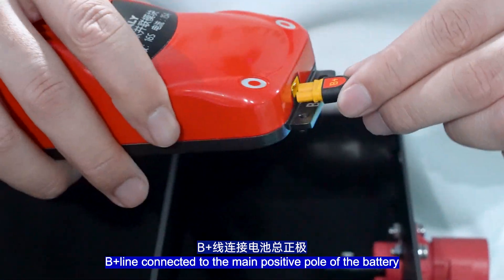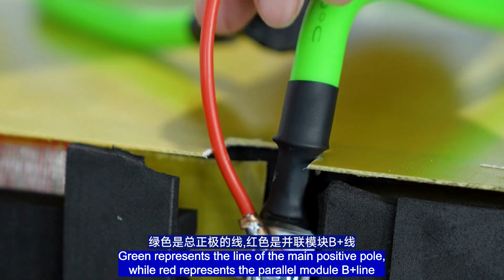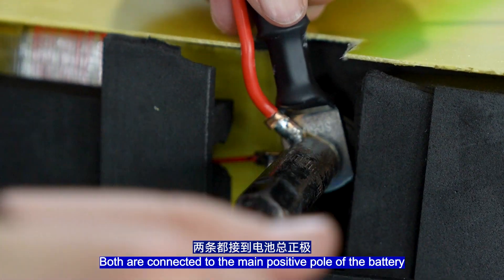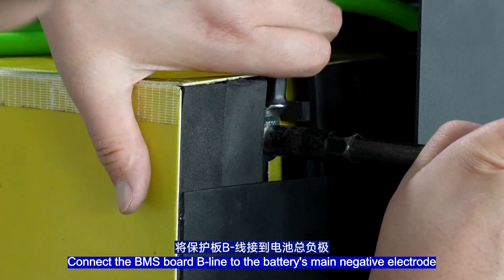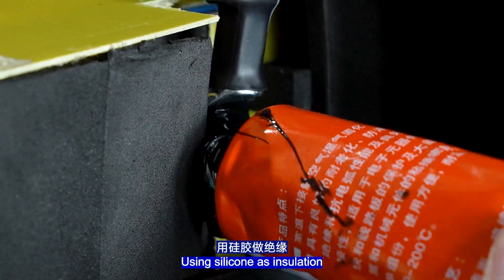Connect the B+ line to the main positive pole of the battery. Insert the communication port of the BMS. Green wire represents the main positive pole line, while red represents the parallel module B+ wire — both are connected to the main positive pole of the battery. Connect the BMS B-wire to the battery's main negative electrode, using silicone as insulation.